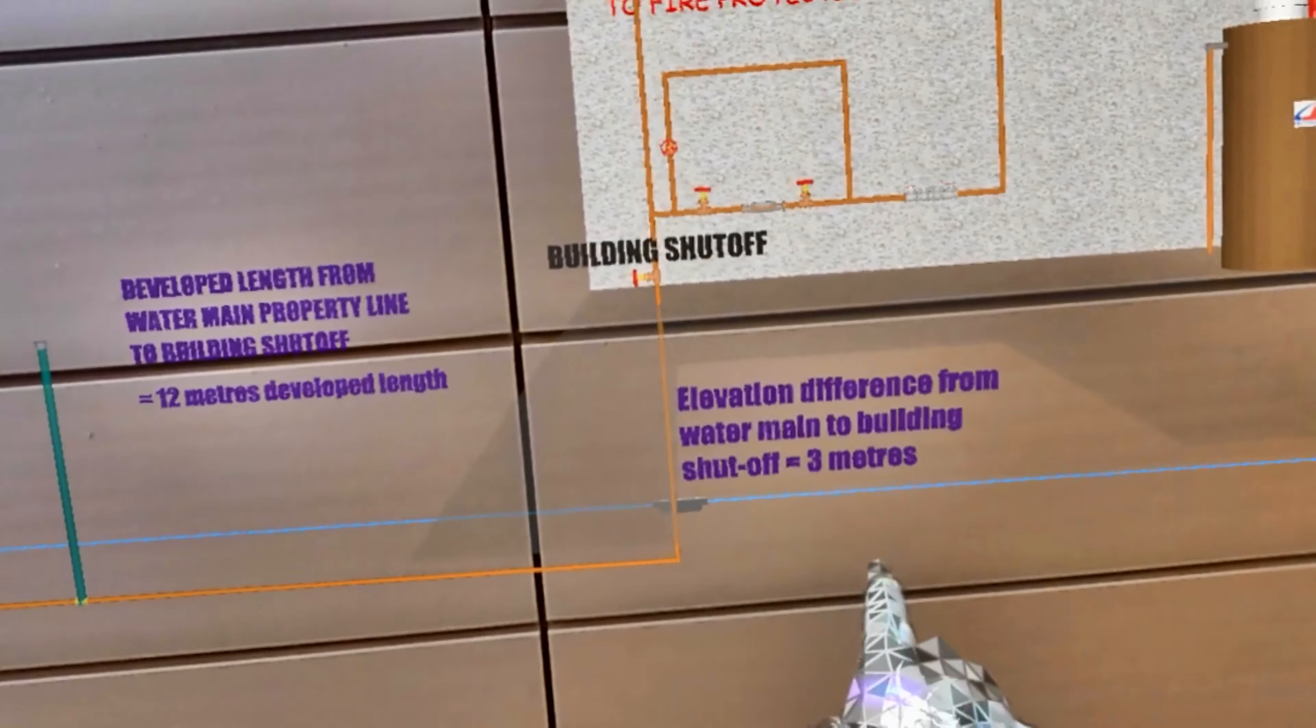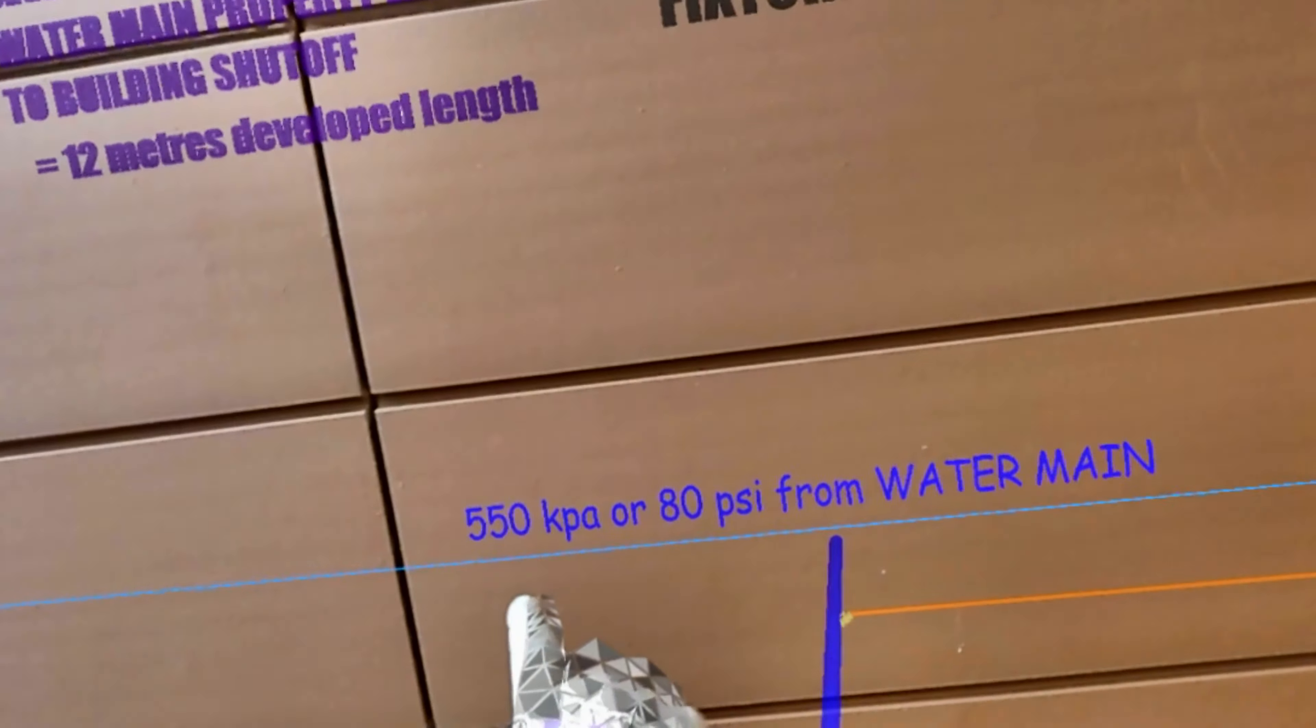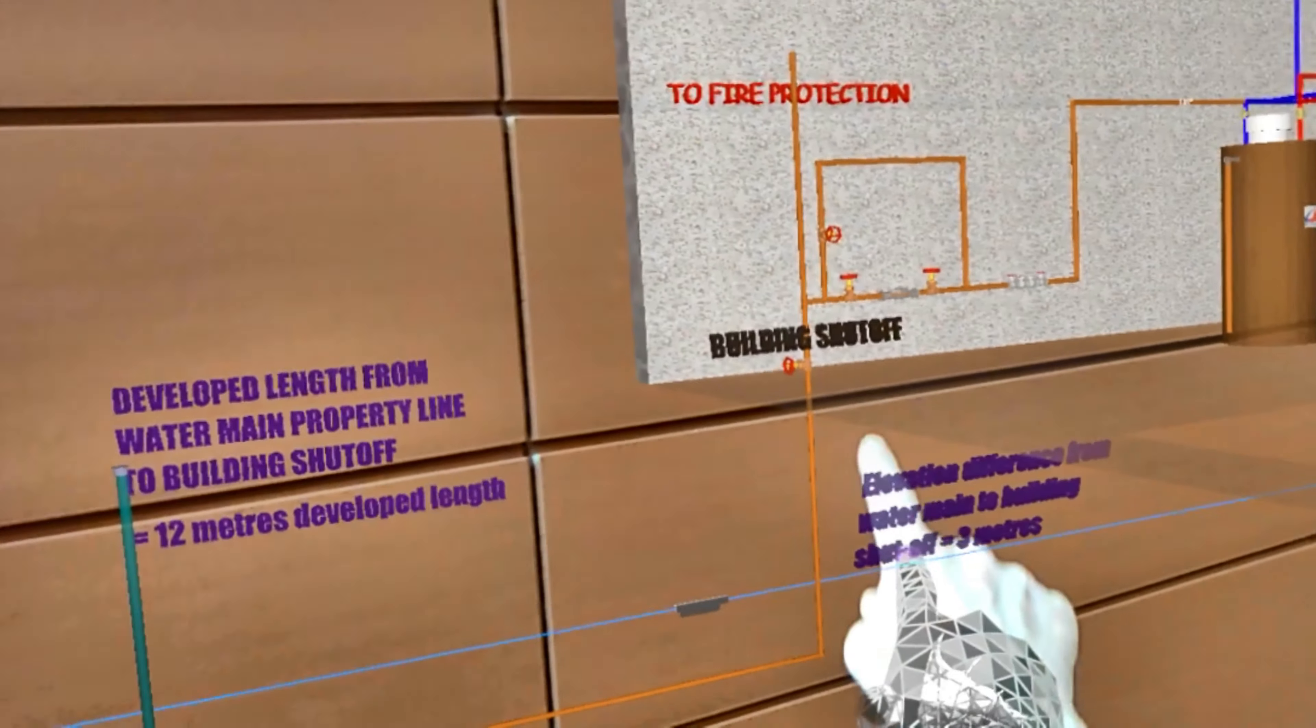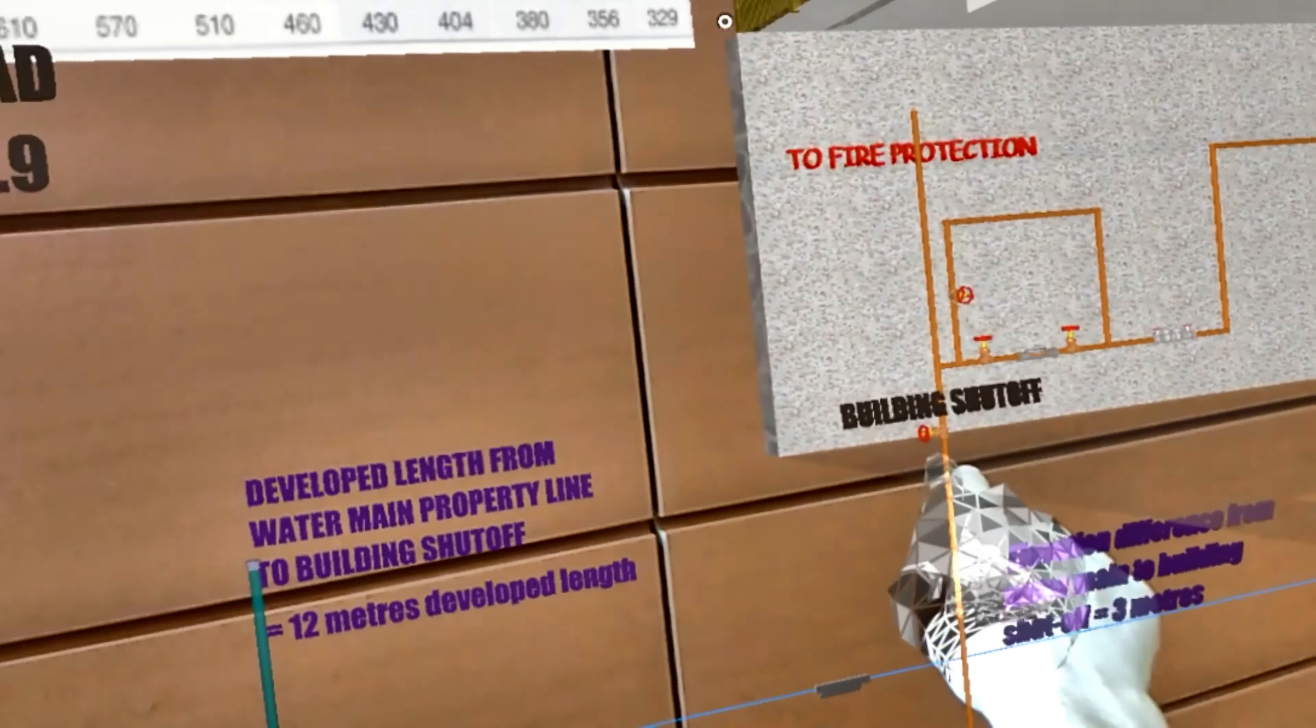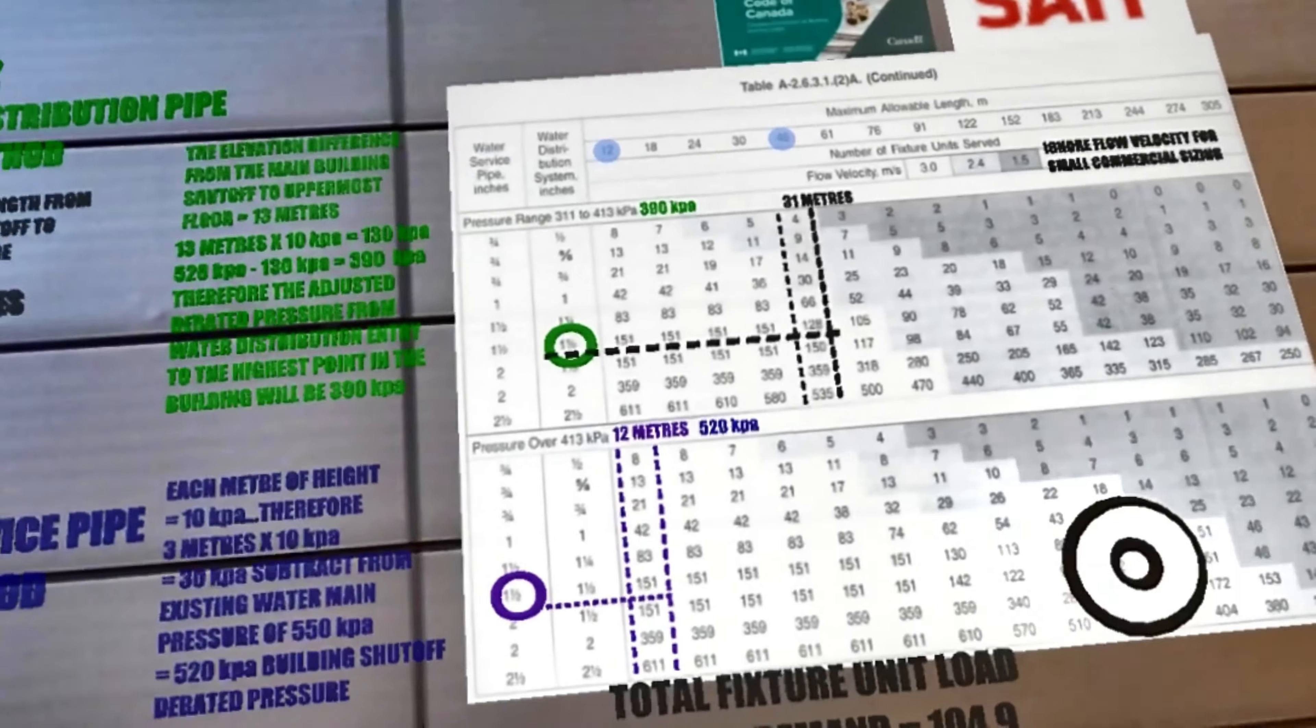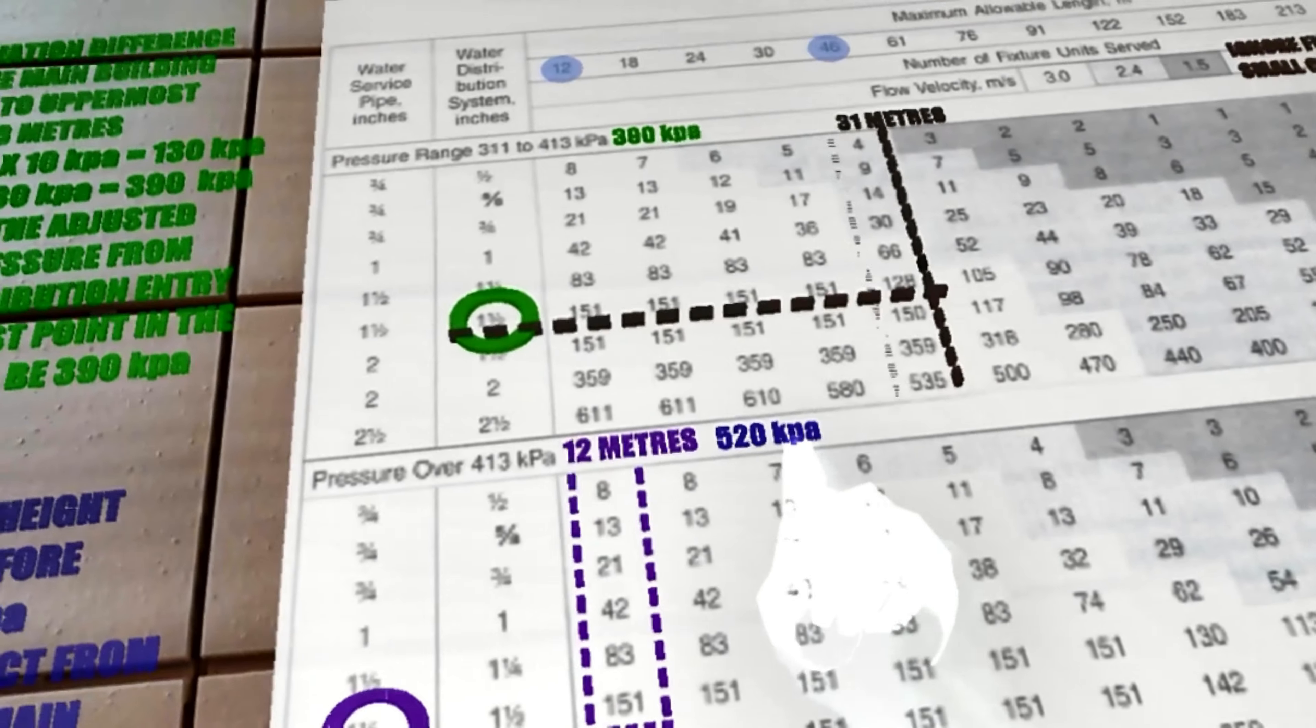And every meter is worth 10 kPa, so you go over here to the water main. This is 550 kPa. You subtract the 30 kPa from here and the new elevated pressure will be 520 instead of 550. So you use the 520 and you go to this chart here which is over 413 because ours is 520, so this is the chart we use.